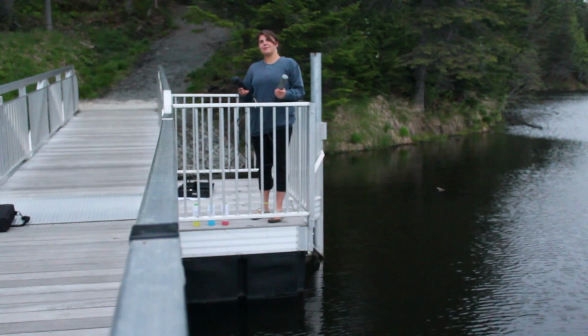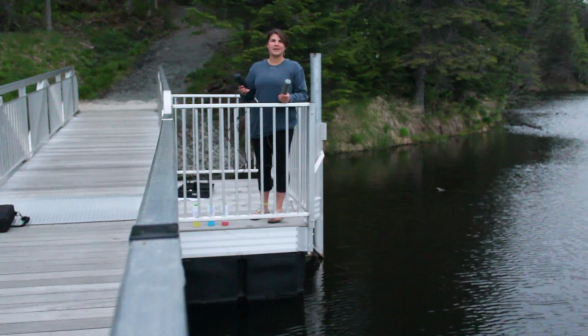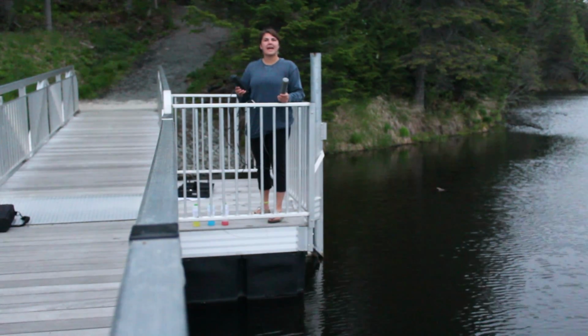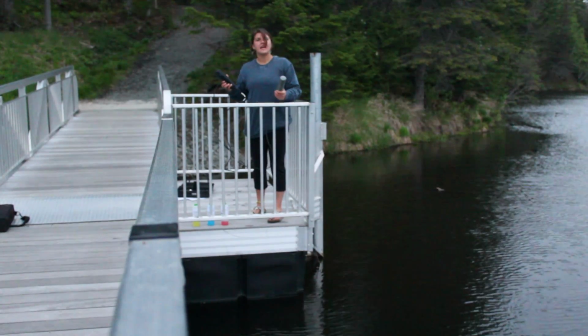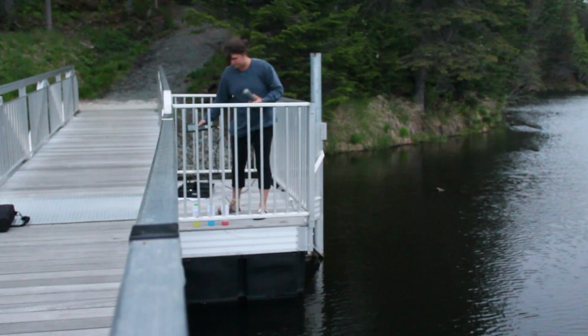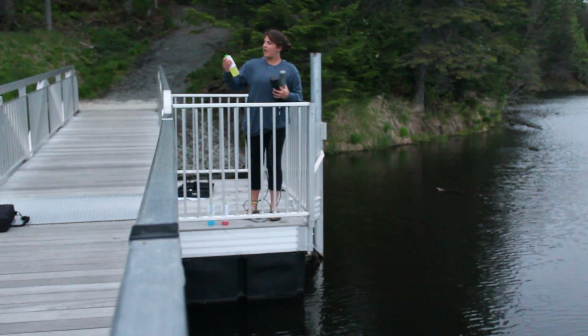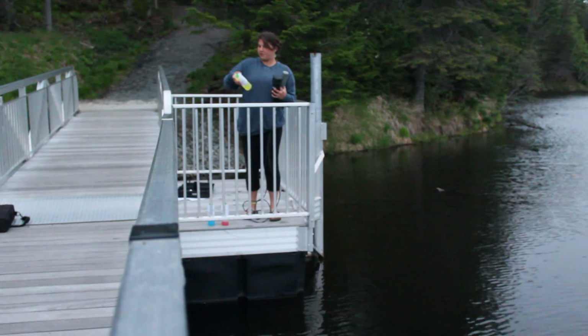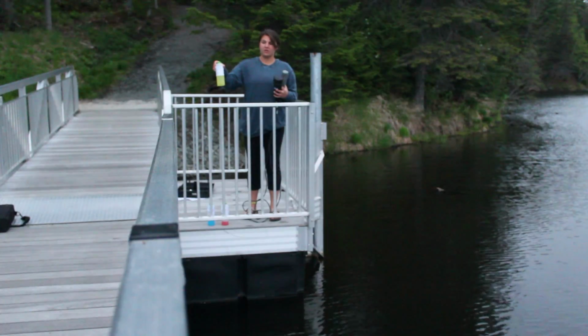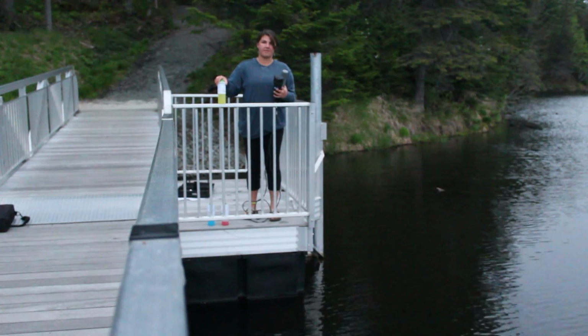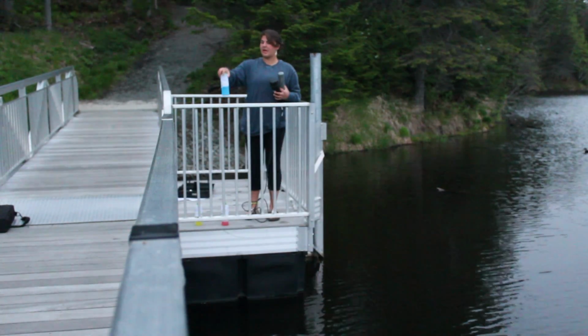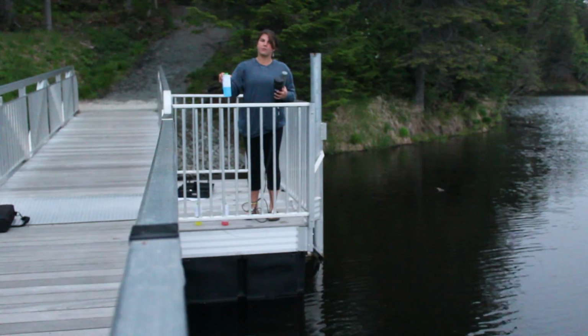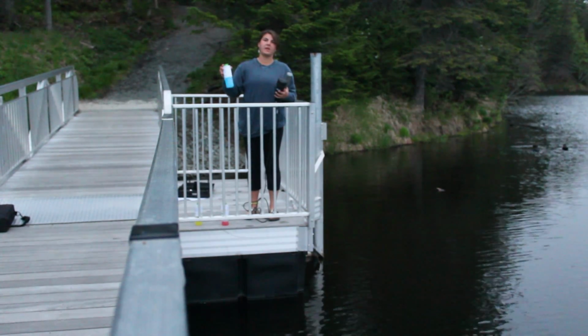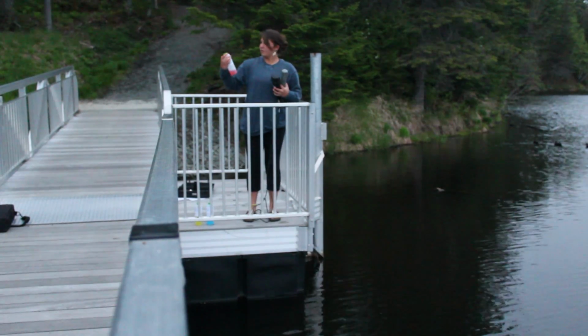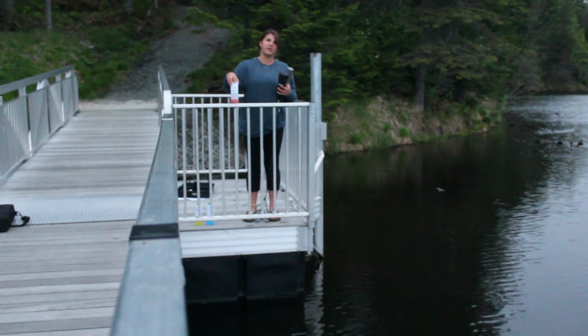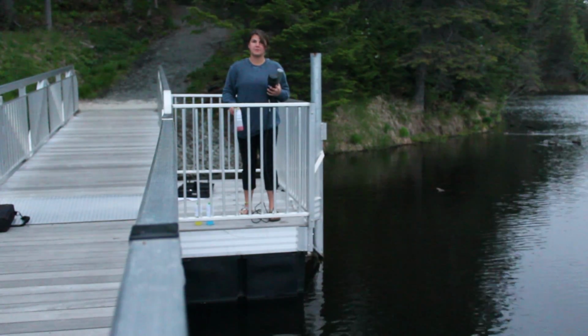I'm Abby Bartlett, and we're going to be talking about the Pro Plus today, the YSI Pro Plus. And we're going to be talking about how to calibrate it because we have a pH reading that we need to do. And it's already been calibrated, so I'm not going to do it, but I'm going to show you how to do it. So each of these bottles has a known pH, and this one has a known pH of 7. So you put this into another bottle, and you would dip the probe in, and it would tell you if it's a 7. And this one is a pH of 10. So you dip it into the liquid that is in its own container, and it should read you a pH of 10. And then there's this one, which has a pH of 4. So this one will go into its own container too, and it should read you a 4. And after that has been done, it should be calibrated.